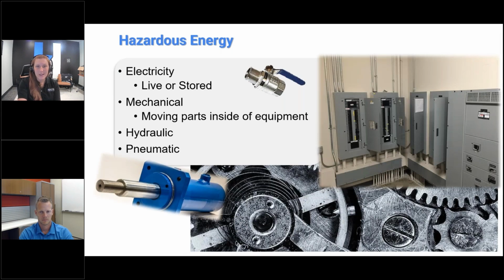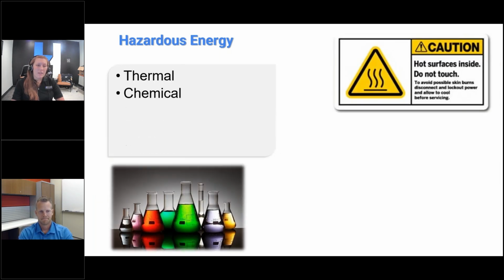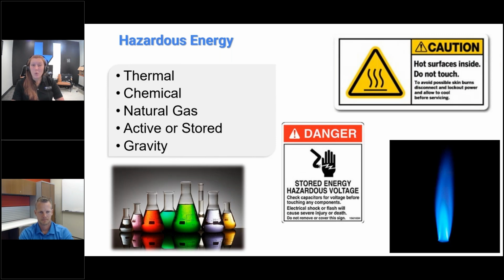So this is one thing you have to realize: we don't always work in a bubble. Maybe electrical isn't the only hazard you have to face. Think about it. There's of course electricity, live and stored, both active and stored energy. Mechanical parts, often there's moving parts inside of equipment or nearby. Maybe you've got an assembly line or a belt system that's near your control panel that you're working in. Make sure that those aren't going to be operating and hazardous and you're within a pinch point area. Maybe some hydraulics, pneumatics in the area that you have to worry about, depending on what you're working on. Of course, thermal, maybe you need some time for that equipment to just cool off before it's safe enough to approach and get in there. Chemicals, natural gas, active or stored energy, as in springs, for example, and gravity. People always seem to forget gravity.